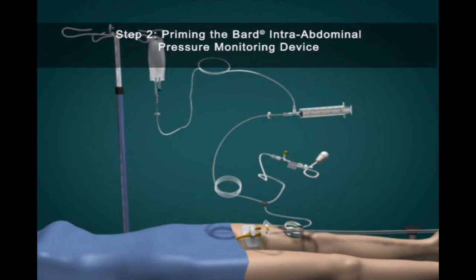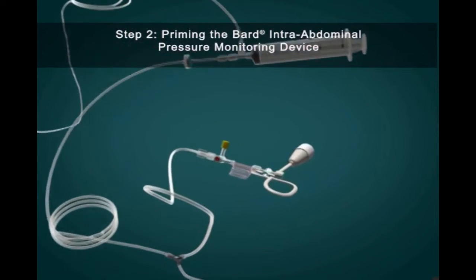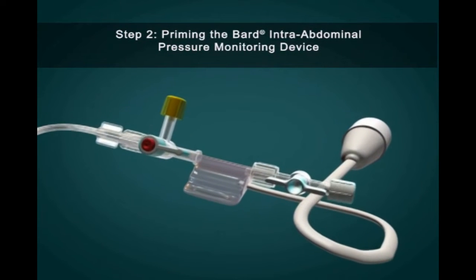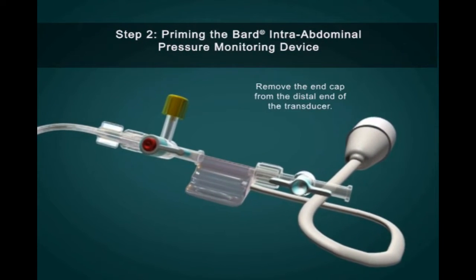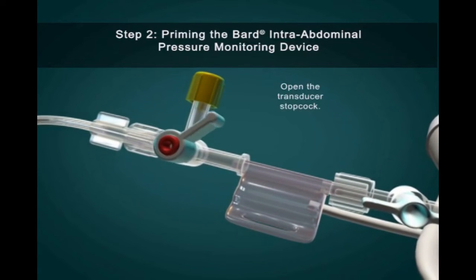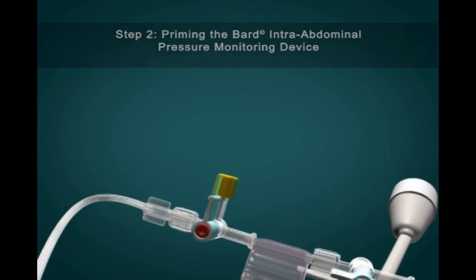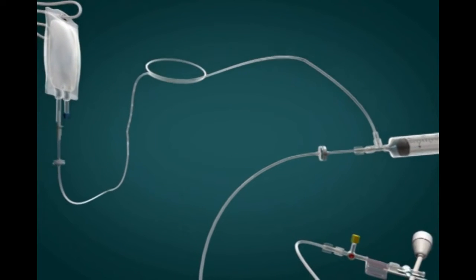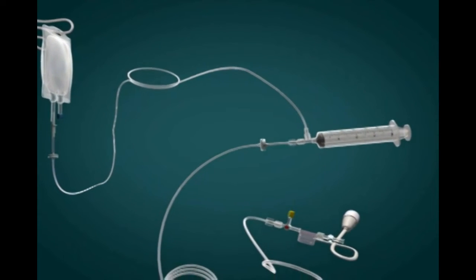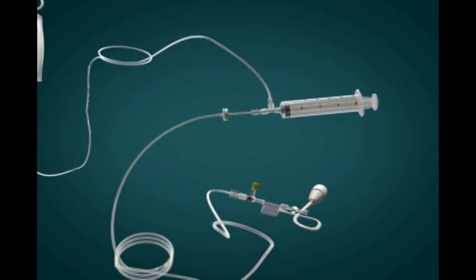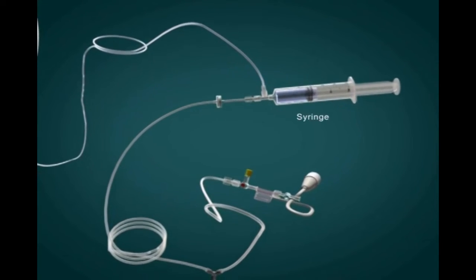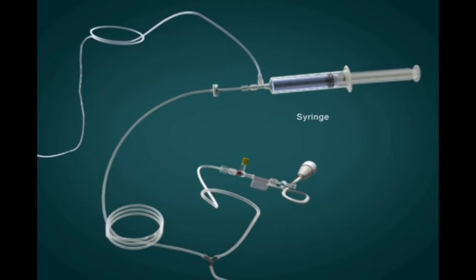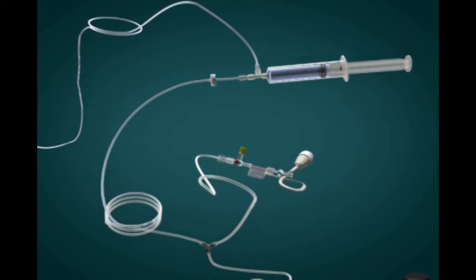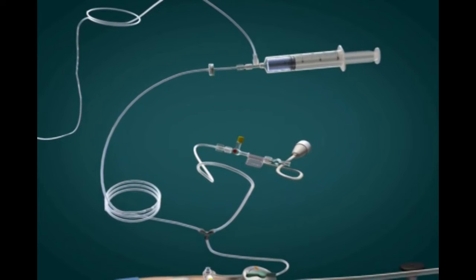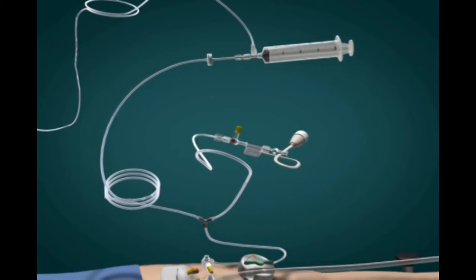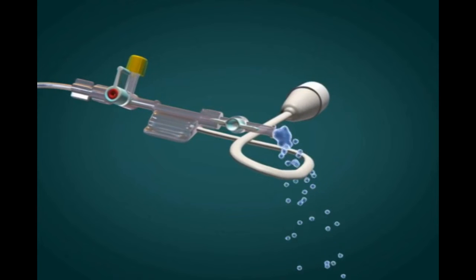Step 2. Priming the intra-abdominal pressure monitoring device. Remove the end cap from the distal end of the transducer. Open the transducer stopcock. Aspirate approximately 30 milliliters of saline into the syringe and compress the syringe. Observe fluid passing through the distal end of the transducer. Ensure no air bubbles remain in the tubing to the transducer. Close the distal transducer stopcock.